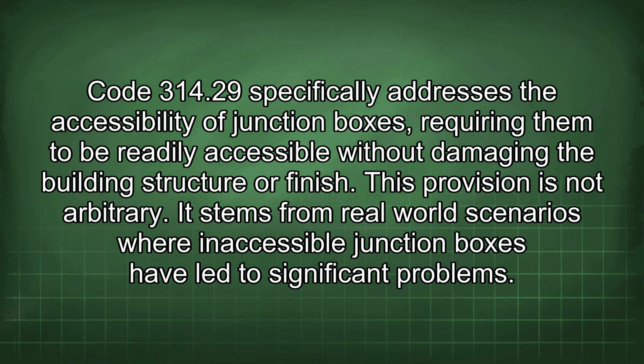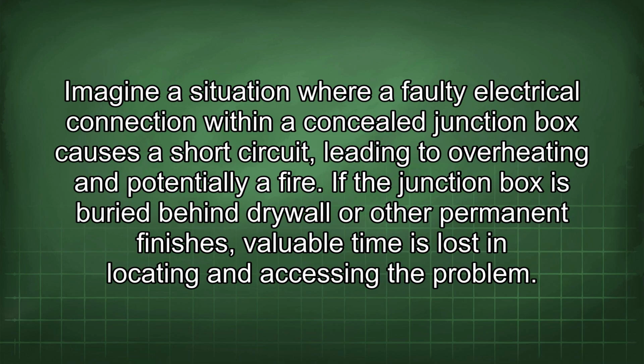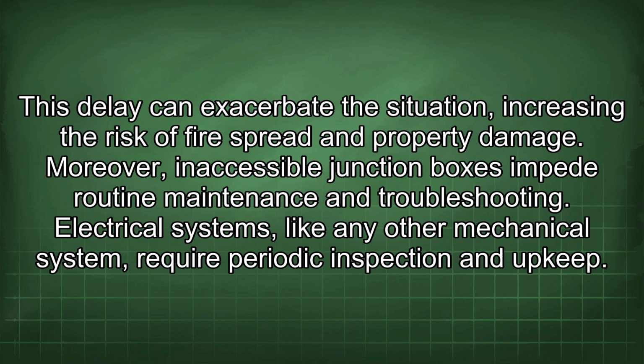Code 314.29 specifically addresses the accessibility of junction boxes, requiring them to be readily accessible without damaging the building structure or finish. This provision is not arbitrary. It stems from real-world scenarios where inaccessible junction boxes have led to significant problems. Imagine a situation where a faulty electrical connection within a concealed junction box causes a short circuit, leading to overheating and potentially a fire. If the junction box is buried behind drywall or other permanent finishes, valuable time is lost in locating and accessing the problem. This delay can exacerbate the situation, increasing the risk of fire spread and property damage.